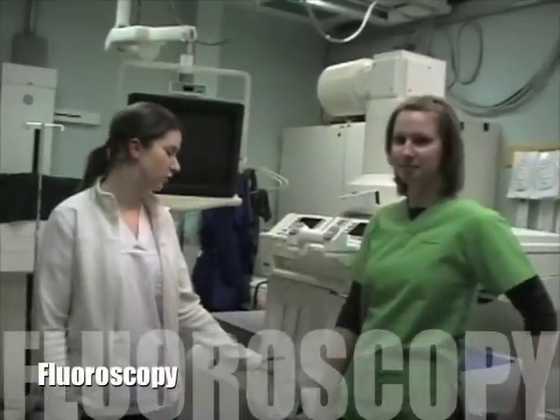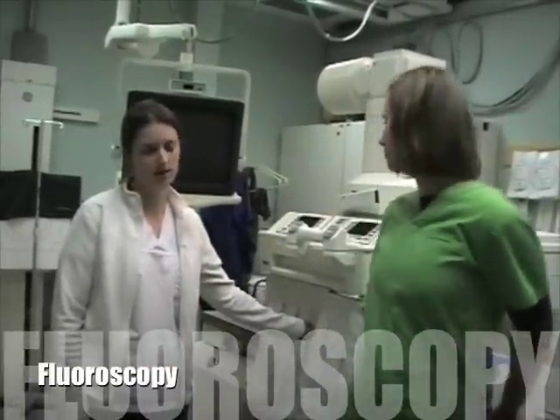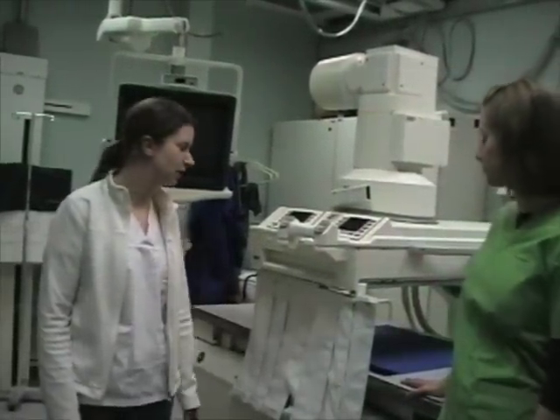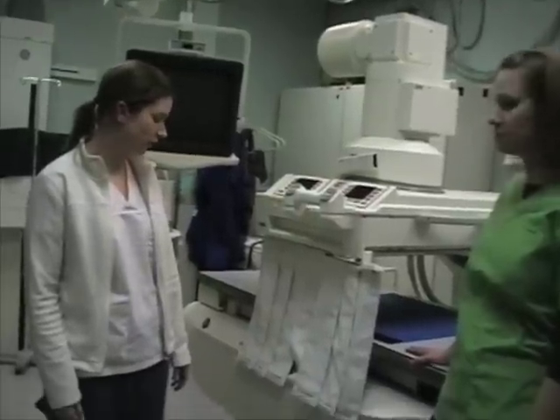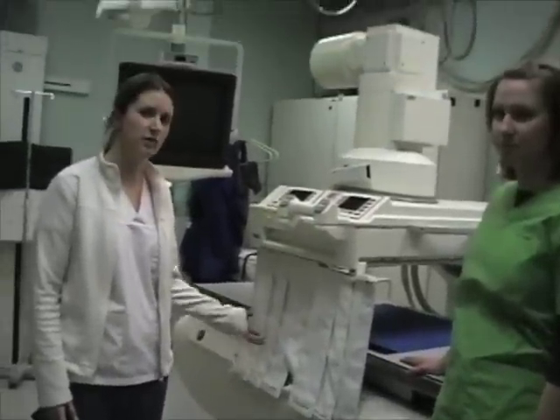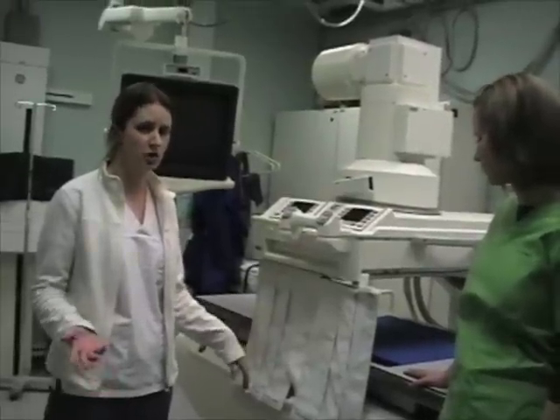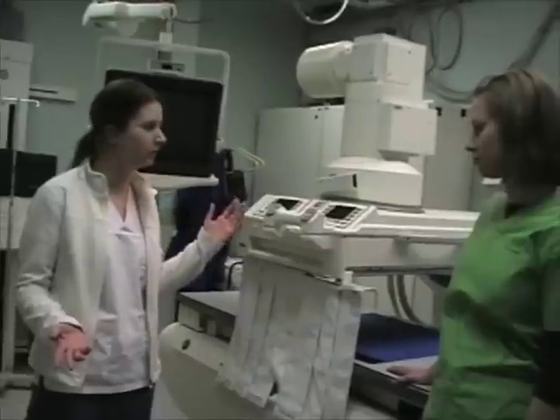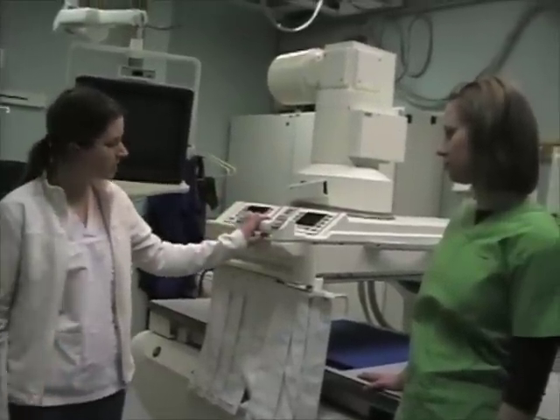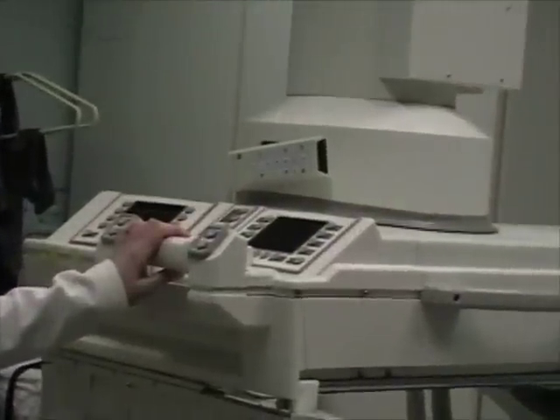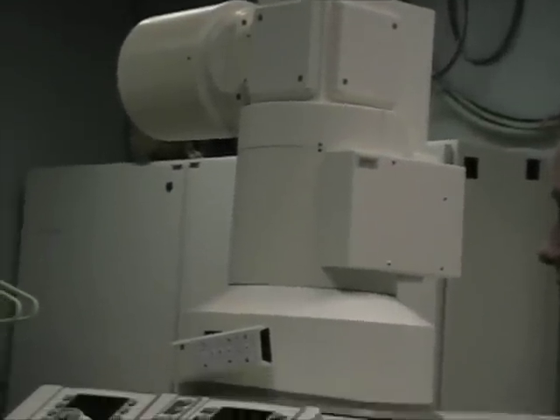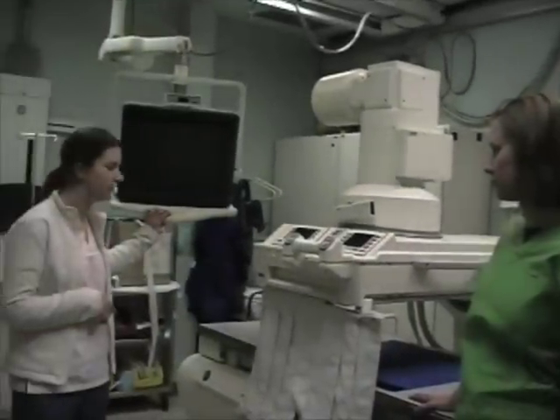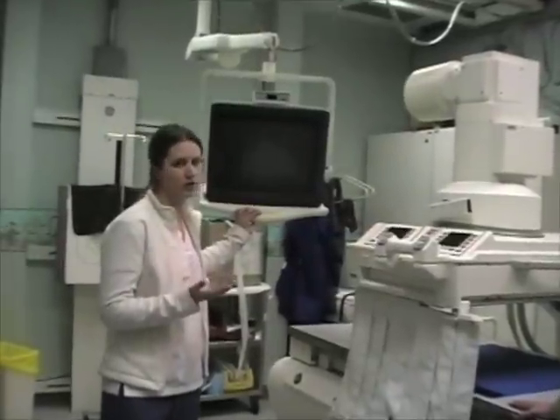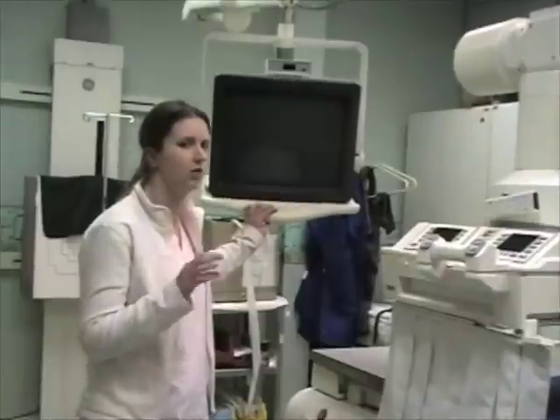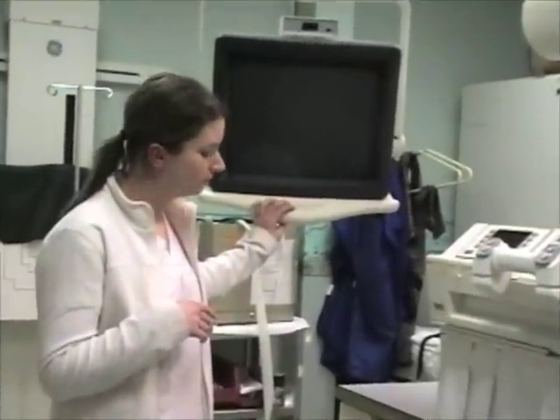This is a fluoroscopy room. This is used for functional studies, such as with the gastrointestinal system. This equipment is an under-table tube equipment, which means that the x-ray tube is actually underneath the table, as opposed to the general room that we saw where the x-ray tube is above the table. This equipment on the top is called an image intensifier, and what this does is it actually captures the x-rays that come up through the table, and it converts it into an image, which then appears onto the television screen. So this is basically a live, real-time imaging as opposed to just a single image in the general room.